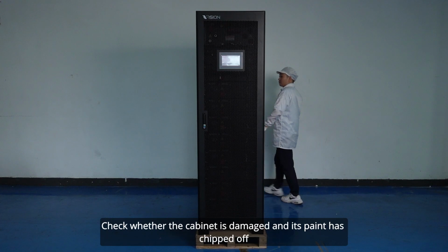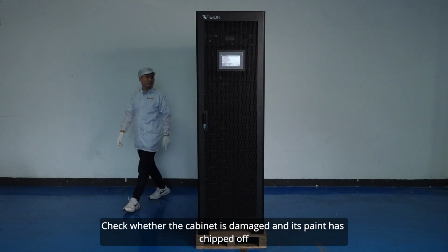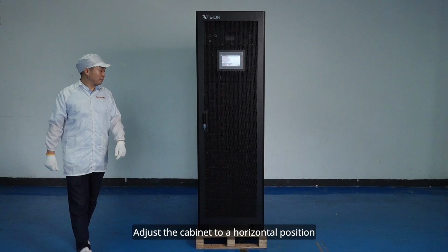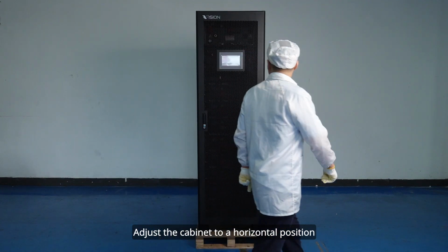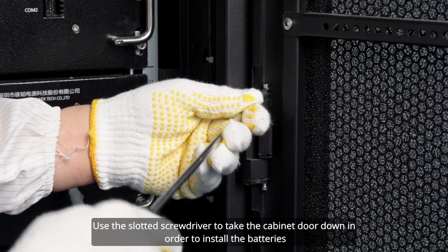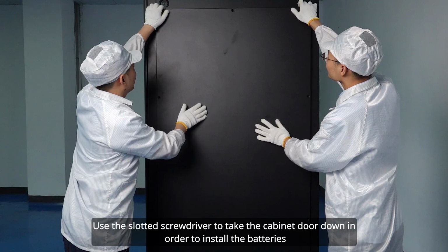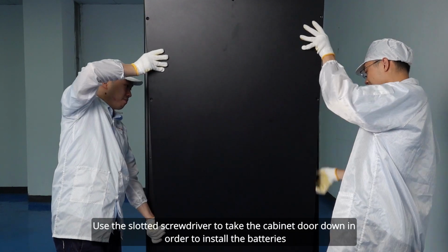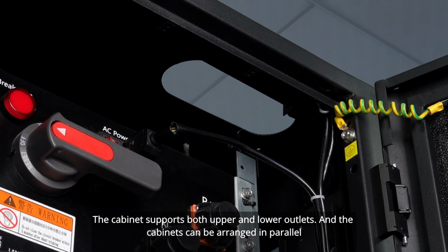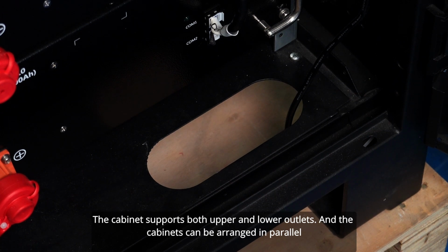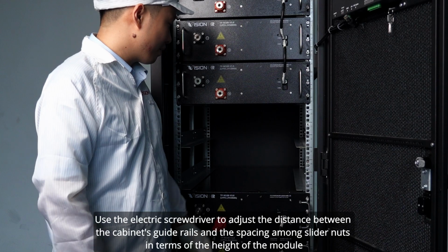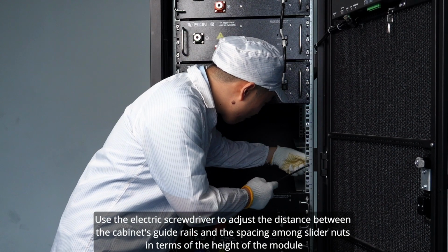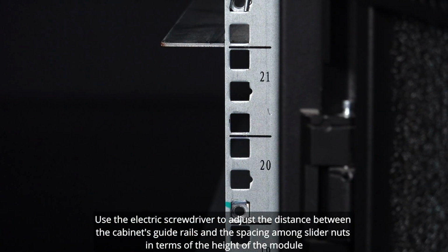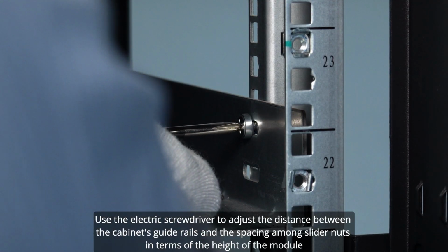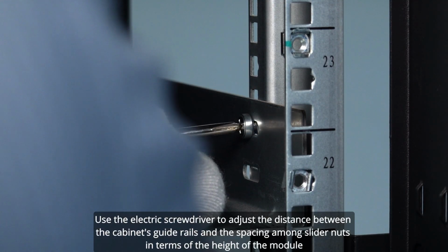Step 2. Cabinet installation. Check whether the cabinet is damaged and its paint is chipped off. Adjust the cabinet to a horizontal position. Use the slotted screwdriver to take the cabinet door down in order to install the batteries. The cabinet supports both upper and lower outlets, and the cabinets can be arranged in parallel. Use the electric screwdriver to adjust the distance between the cabinet's guide rails and the spacing among slider nuts in terms of the height of the module.